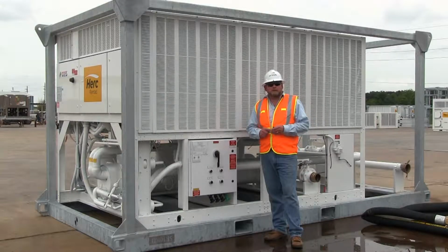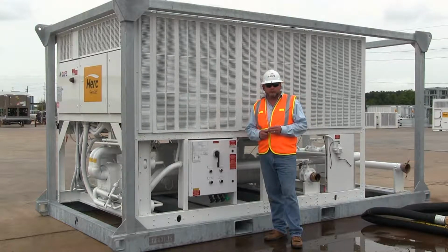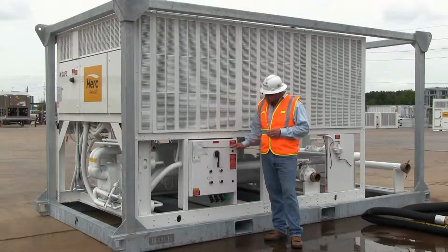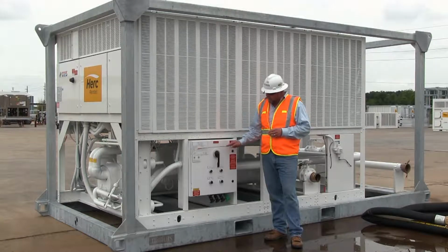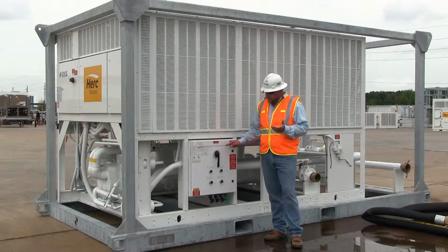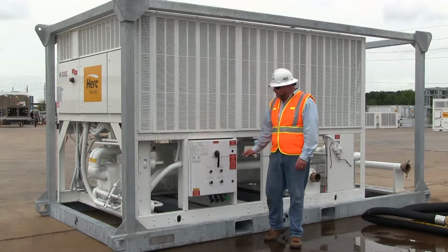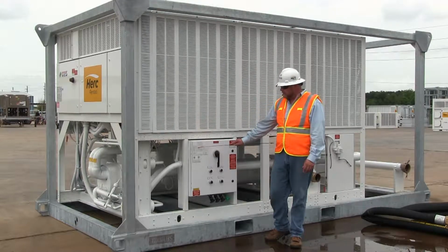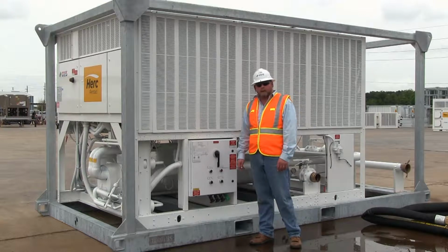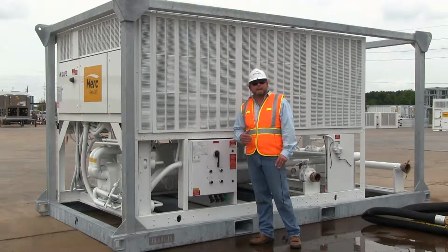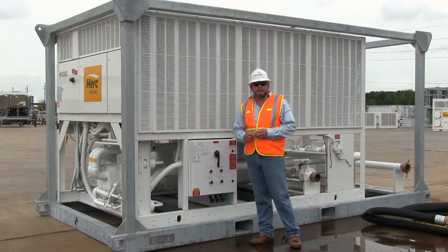Okay, the next part of our setup is to determine the power requirements. This machine takes 460 volt three-phase, 60 hertz power. If you look at the main CAPS product data tag, you'll see that we have clearly stated the MCA, minimum circuit ampacity, as well as the maximum overcurrent protection. This particular 100-ton chiller takes 244 amps minimum circuit ampacity or 250 amp MOCP.